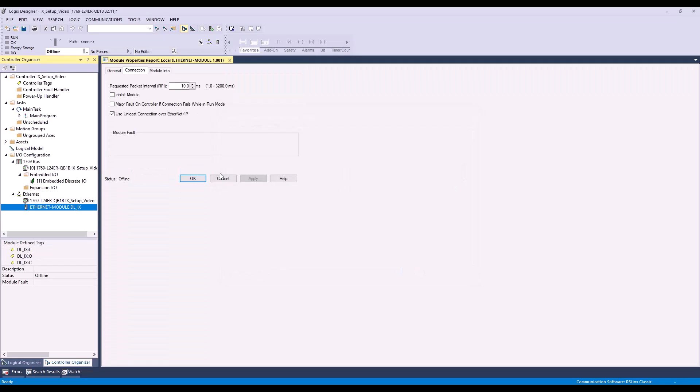Now we'll set our connection parameters. Set your assembly instance input to 100, output to 101, and configuration to 1. Set your input size to 42, output size to 2, and configuration size to 0. Also, make sure you have your communication format set to DINT. Now press OK.